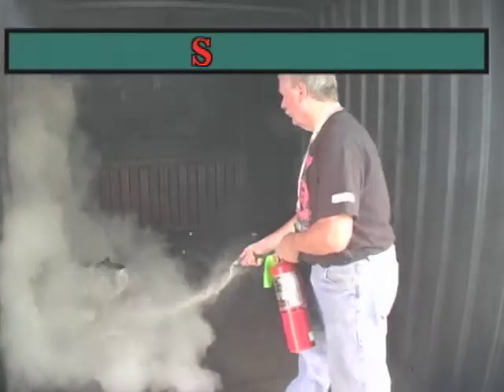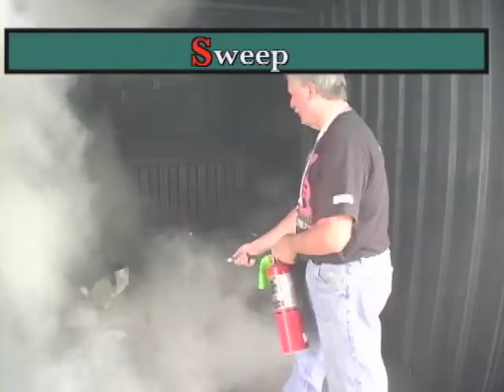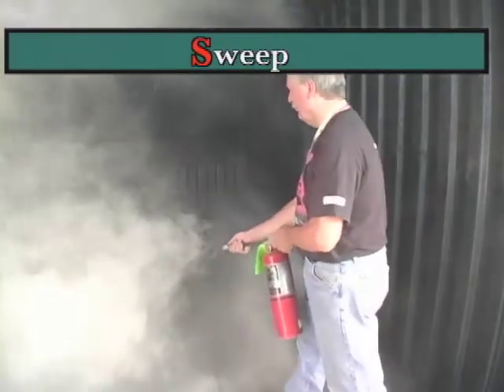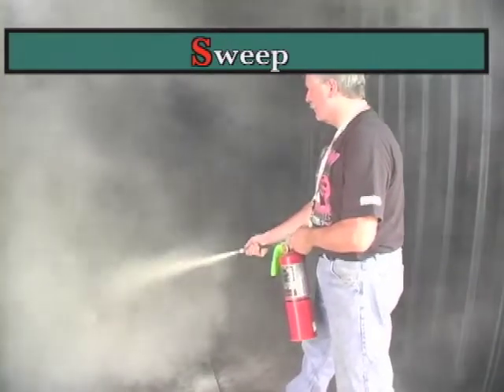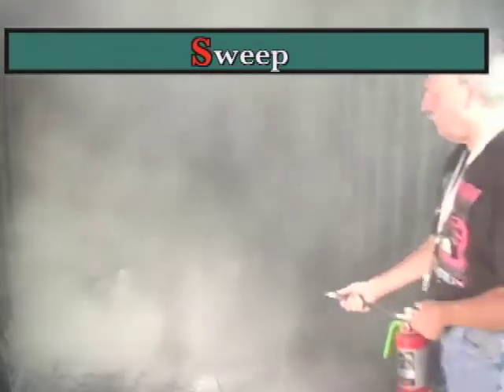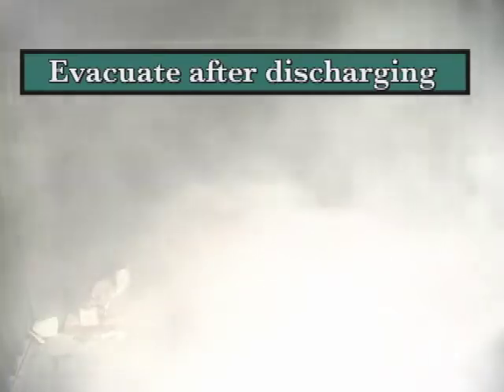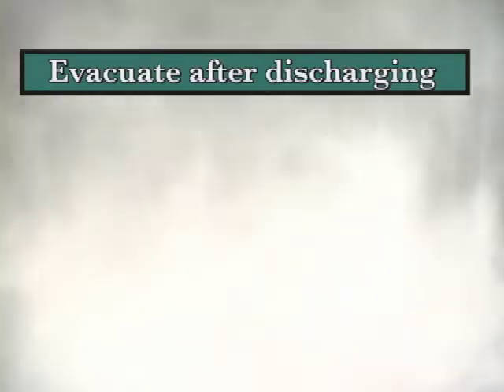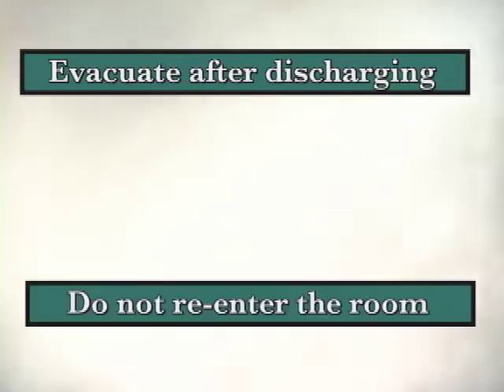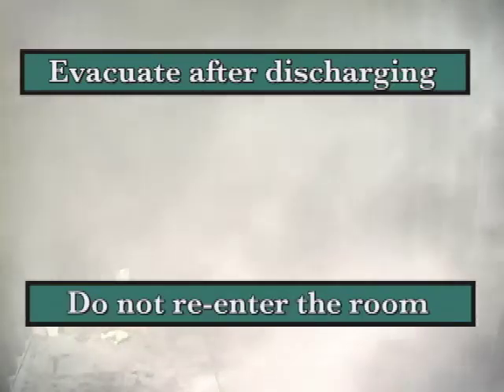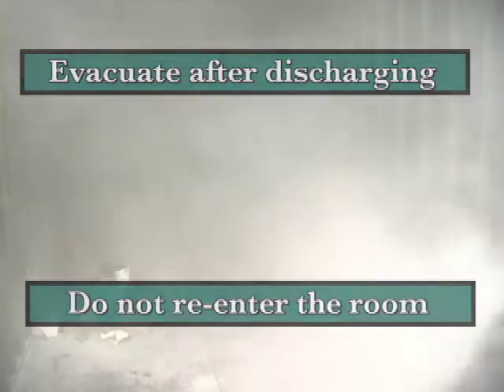The final S stands for sweep. Sweep the nozzle back and forth to extinguish the fire. Continue to sweep until the fire is extinguished or the canister is empty. If the fire is not suppressed with one extinguisher, evacuate to an area of safe refuge and wait for fire response personnel. Never re-enter the area once the extinguisher is empty and the door is closed.